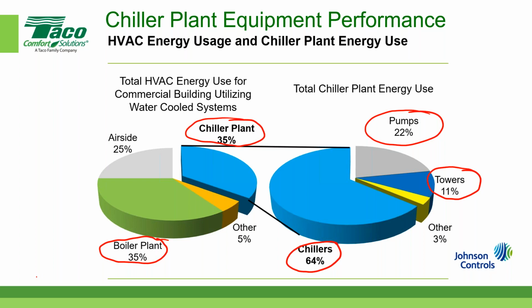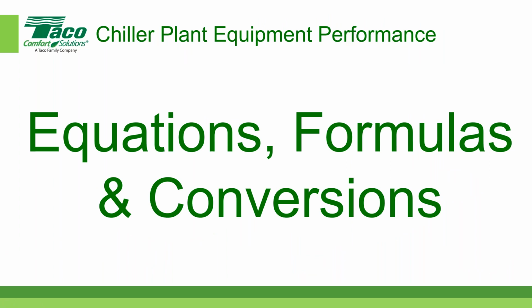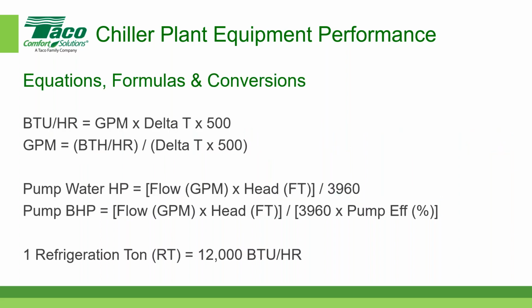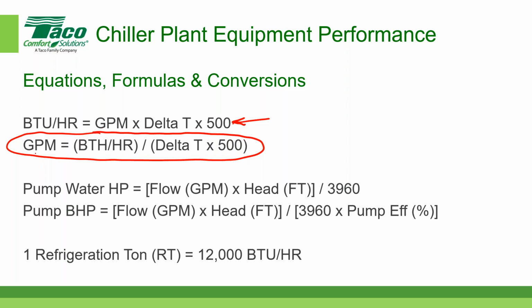Okay, so let's dive into the chiller first. And let's see if we can erase this. Yep, we can. Look at that, Brett. That's amazing. Off to a good start. Yeah, so again, for the equations and formulas, I'm just going to put them on the screen. I just want to highlight a couple. This one here, the one at the top of the screen, or a variation of it, is the one that we use most in the hydronic world, and that is we're interested in what's happening with the flow in gallons per minute. And if we have the load in BTUs per hour, we divide that by the delta T and by 500, that's how we can get the GPM.